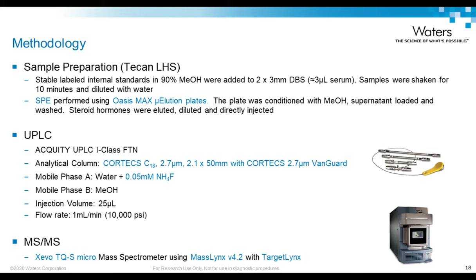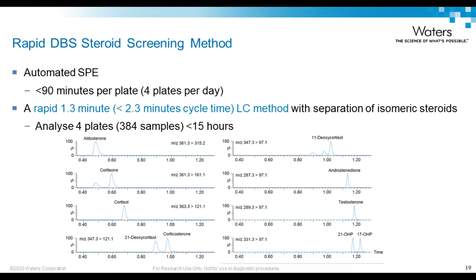Utilizing all the technologies available to us, automation of this SPE protocol was performed in less than 90 minutes per plate, allowing for extraction of 4 plates in a typical working day. A rapid 1.3 minute LC-MS method with a cycle time of less than 2.3 minutes was created with the separation of the relevant isobaric steroids, including 11-deoxycortisol, corticosterone, and 21-deoxycortisol. This allows for the analysis of 384 samples in less than 15 hours using LC-MS/MS.